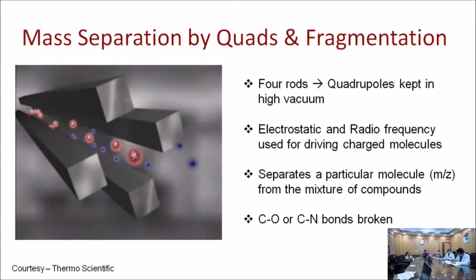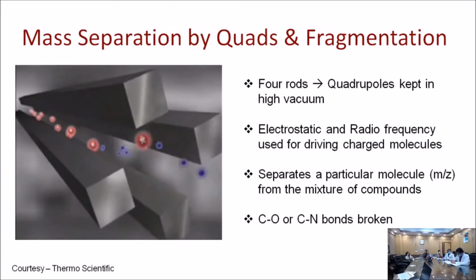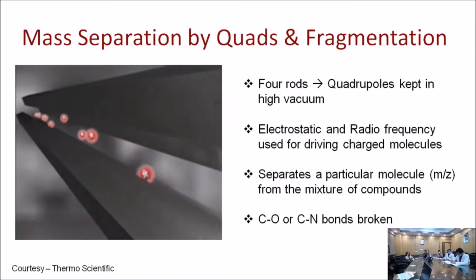The fragmented ion goes inside the quadrupole, and the quadrupole continuously transmits ions. A molecule of your interest only goes inside, all others go out. This is how the quadrupole separates a molecule based on its mass to charge ratio.